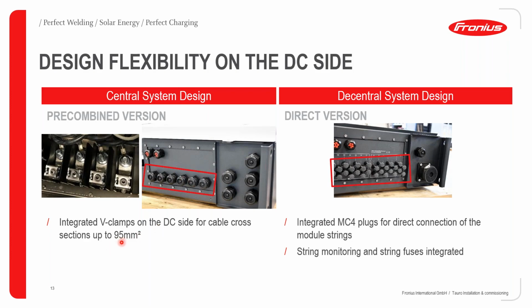When it comes to ordering the Tauro inverter, you are going to order from Fronius either a pre-combined version, and this is the version that is going to do centralized topologies, or a direct version, or D version, which is going to be used to do decentralized topologies. So how to distinguish the two is the fact that if you look at the back of the inverter, for a pre-combined version, it means that all your strings are pre-combined before they're coming into the inverter. You have an area for DC power connection that has about 6 cable glands where these cables can go through. And then inside the inverter, you have the DC V clamps where you connect your DC plus and minus coming from your string array.